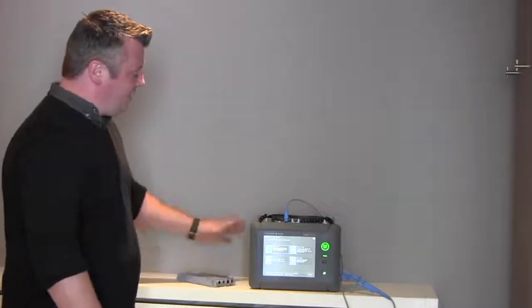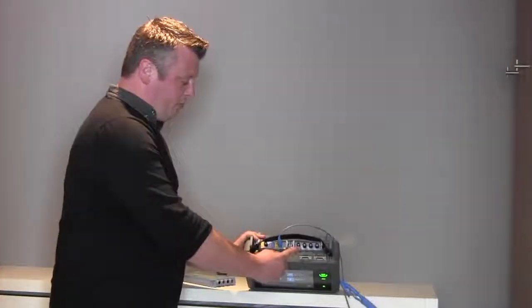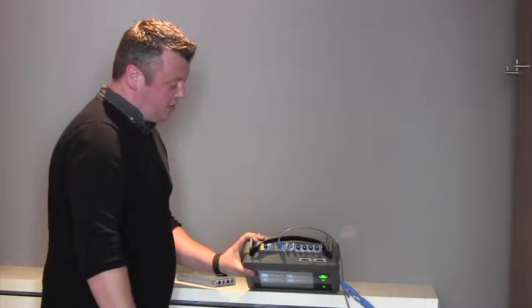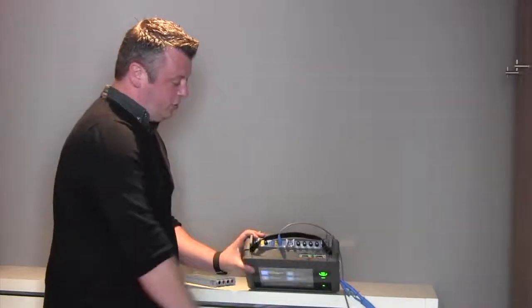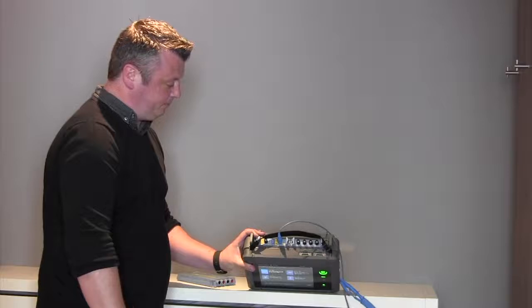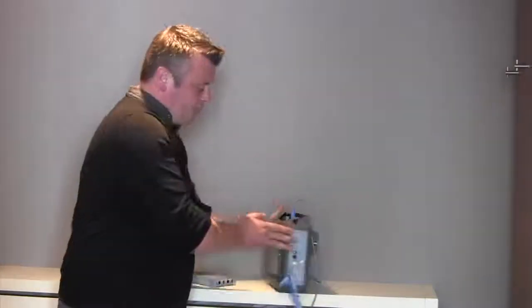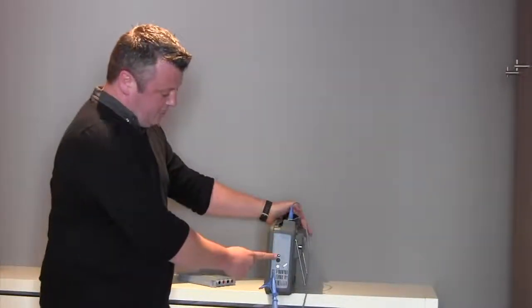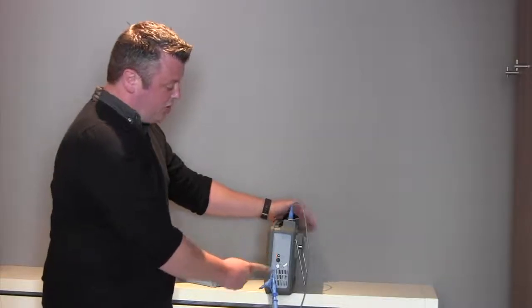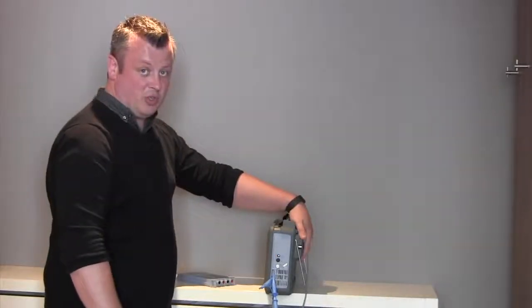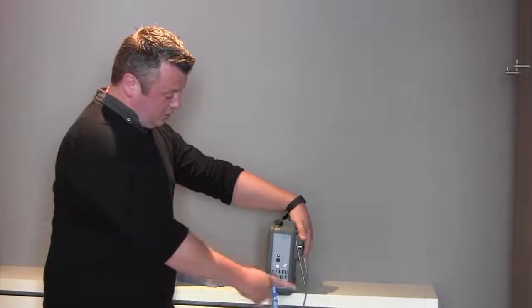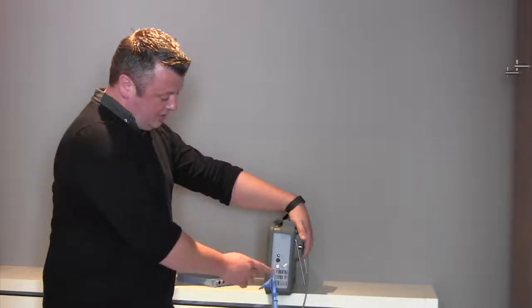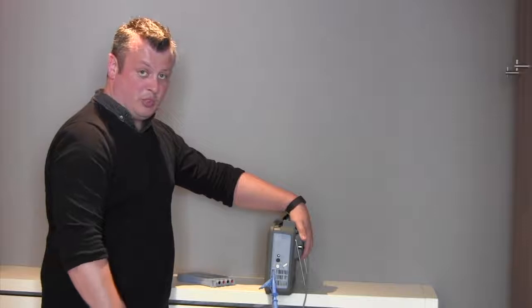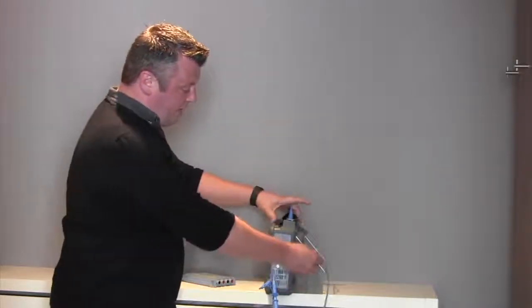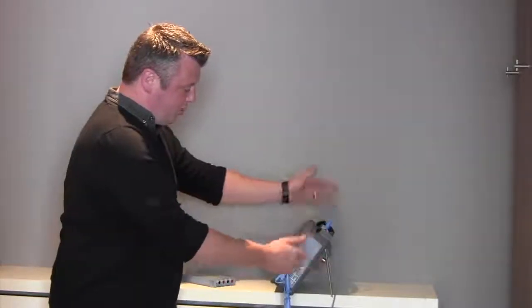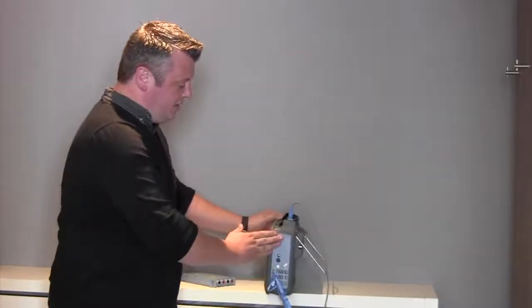The 350 I have with me here today allows for two input modules to be inserted into the top, and it also comes with two logic channel inputs as well. Around the side of the instrument we have a recharging port which will recharge the battery, which is one of the options on the DL350. We also have a calibration source here, also a fuse and a grounding point too. Around the back we have a support stand which supports the weight fully of the DL350.